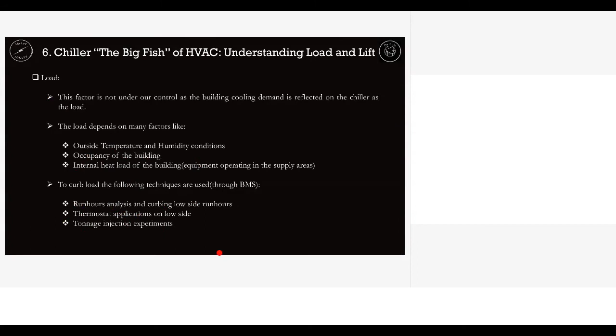Coming to lift, there are a lot of things. Many people say that lift is actually the most important thing when you speak about centralized air conditioning and how to save energy from it. So your cooling tower should be performing perfectly, giving the best possible approach. So the condenser entering temperature, or the cooling tower outlet temperature, should be as low as possible. In terms of data, less than 90 degrees Fahrenheit, sorry, not Celsius. 88 to 90 degrees Fahrenheit is the normal condenser entry to the chiller, that is the temperature of the water from the cooling tower outlet. And if you can make it lower, it would be even better. The lower it is, the better it is. So that is one aspect, cooling tower outlet or condenser entry, one parameter controlling the lift.